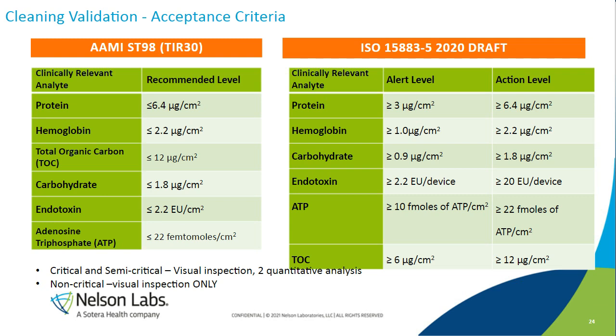Now, on the bottom of the slide, you can see that I've written that for critical and semi-critical devices, you want to have a visual inspection. That is a must, with 2 quantitative analyses. So you have to test at least 2 markers out of this panel that I presented on the slide. The most common is protein. You have to do protein. It's a must. I don't think that is negotiable. And then you would go down the slide where it says hemoglobin, TOC, carbohydrates. I have ranked them by how they should be considered for testing.